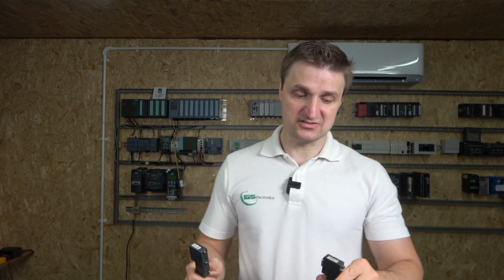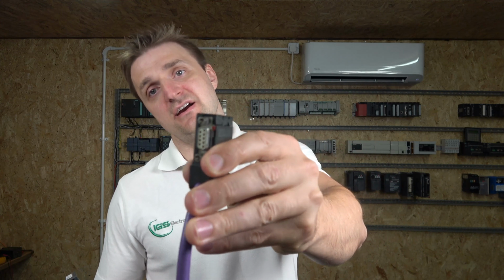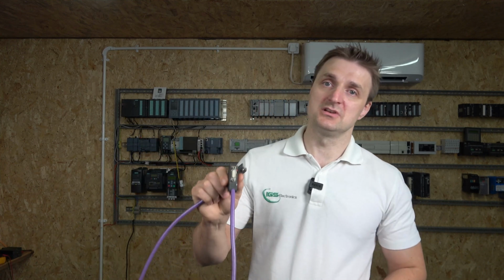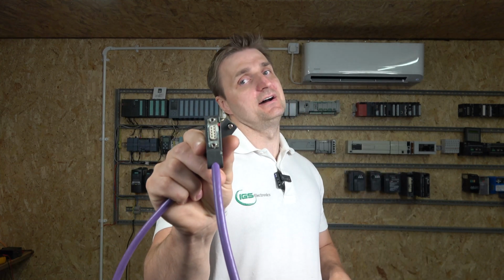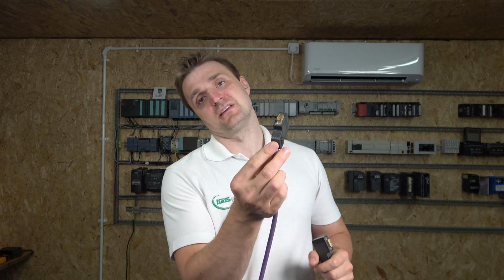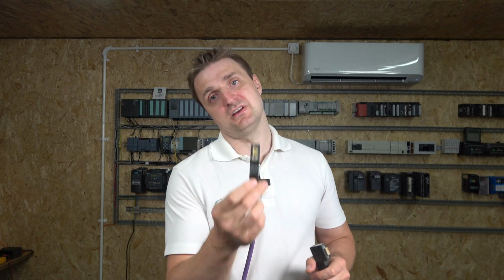Another thing, as you can see in here, I have a programming port there. That port should not be used for spurring off your Profibus. That port should be used only for connecting your programming devices, or whatever else you're trying to do. It's not to be used for spurring off. Using it on another device doesn't mean you cannot do it, but Siemens strongly suggests you not do that. Just use the spurring that is made point to point in here, right underneath.